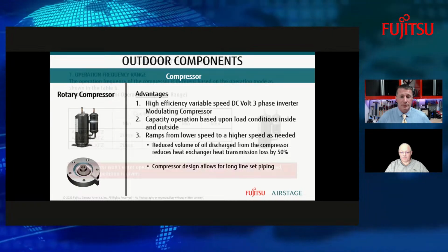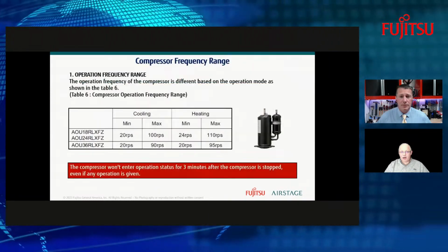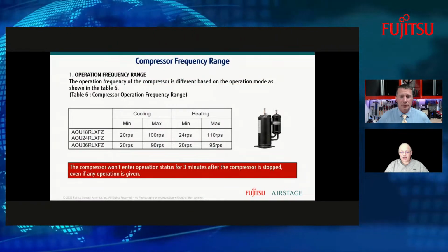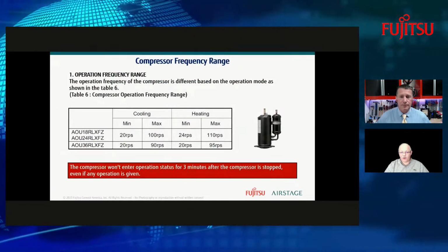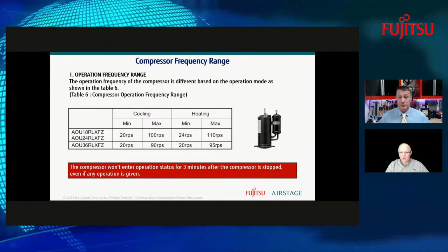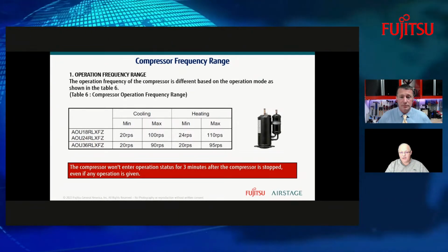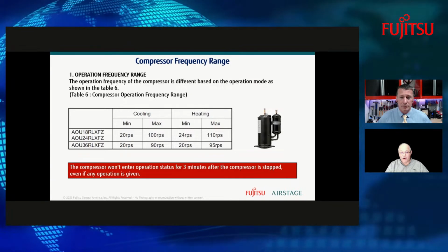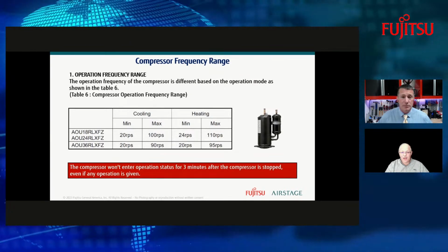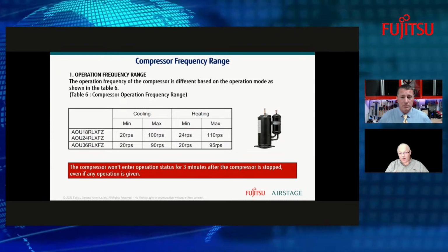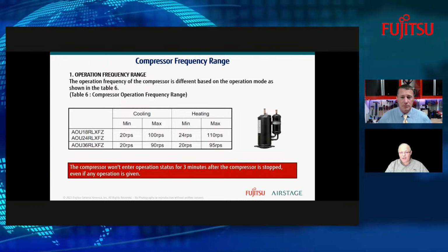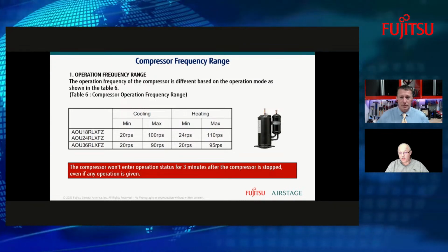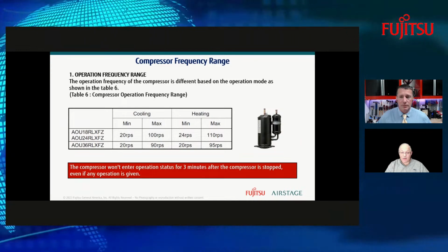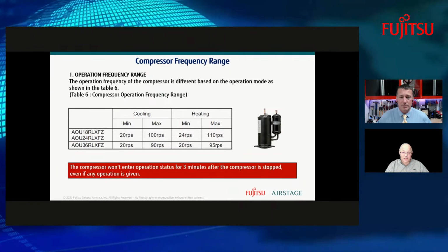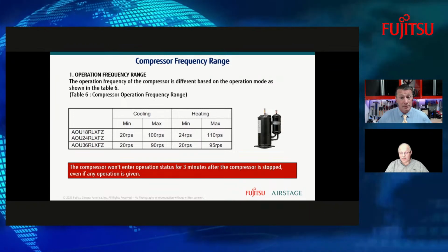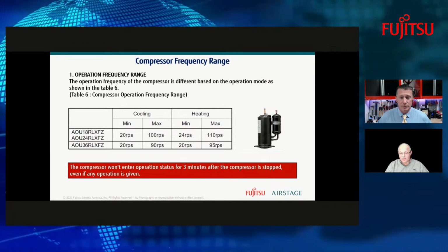Yes, that's correct. So when we start looking at the operation on the frequency range, this is an example of just the models. You can see we've got an 18, 24, and a 36. And both in cooling and heating, now these RPSs, or revolutions per second, of the compressor vary from model to model. Sure. But you see how they have a very low minimum and a higher maximum. And that all depends upon the operating conditions currently. What's the temperature outside? Is it mild? Is it a mild temperature inside? Well, if it is, you can see that we're probably on a mild day not ever going to get to any of these high RPSs that you see for a max.